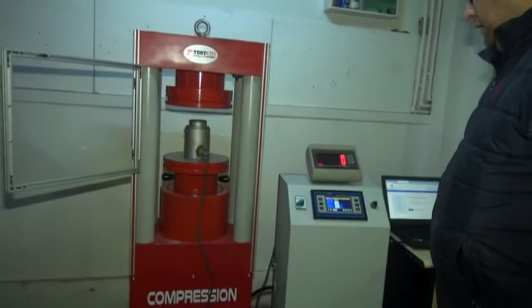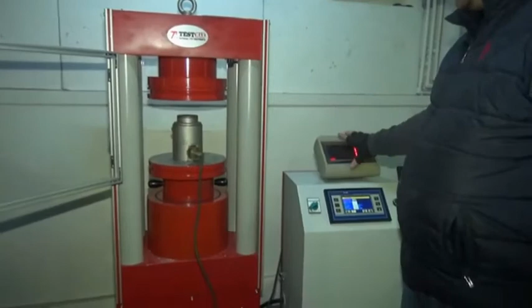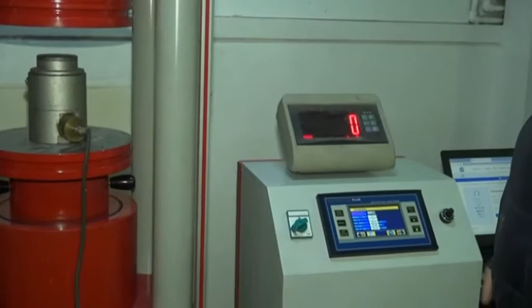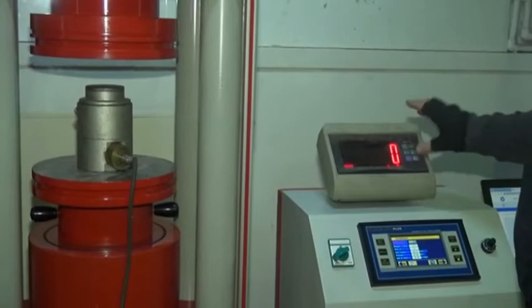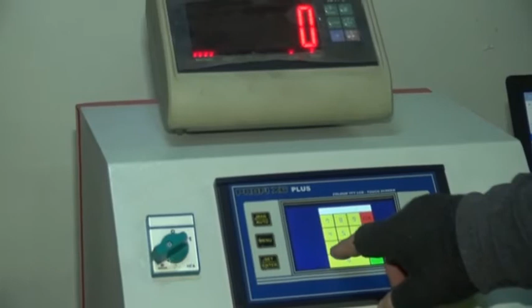I'm going to show you how to calibrate our display unit. Now we need a reference load cell for starting calibration, and a reference calibration unit. And then we place the calibration load cell in our test machine and display 0. Also, we press the setting button on our display. Our settings password is 1, 2, 3, 4. Enter. Now I'm going to calibrate channel 1. Press the channel 1.